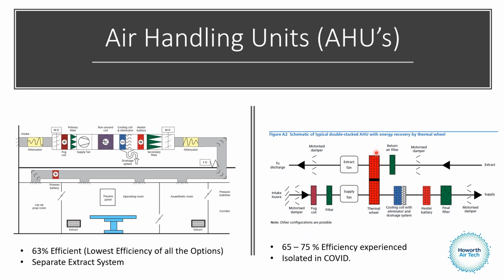The next air handling unit we have is a thermal wheel, and notice that all the components are at the bottom of the air handling unit. That's done on purpose to make maintenance and inspection easier. It's 65 to 75% efficient. During COVID, CIBSE told all institutes to turn these off. However, when you speak to some authorised engineers in the industry, they believe that by the time it's gone through this system and diluted, that argument is irrelevant. HTM03 was written before COVID, but that's just something to consider. Again, I'm no expert when it comes to the transmission of COVID.